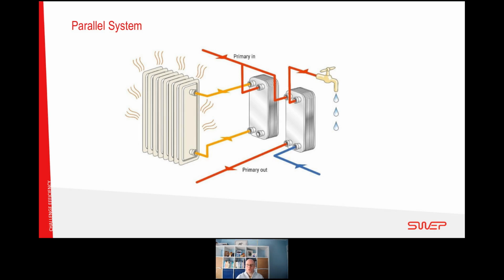So this is what you might call a traditional parallel system. Typical setup. This is also the same for a HIU, but let's say in a substation example, we've got one heat exchanger for the space heating, and then there's the other one on the right-hand side for the domestic hot water. This is still a good solution for the hot water production. We've got the primary flow entering in, you can see in the top left-hand side of the heat exchanger. That then transfers its heat as it flows down to the cold water that's coming in on the bottom right and then going up. So again, a perfectly good and acceptable solution in a district heating scheme, and used quite commonly in HIUs and also in substation systems as well.